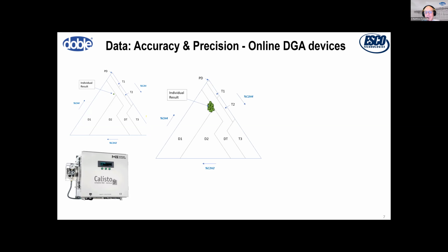But what happens as I start to apply some error? Generally speaking, the error of a GC is around 10 to 15%, and again, this is what we're measuring and seeing. Now we can see that while a lot more results sit in D1, there are a few now in D2, and a few more in DT. That's the overlap between what's called a thermal-style fault and a partial discharge or full discharge-level fault, which could also be acting together.